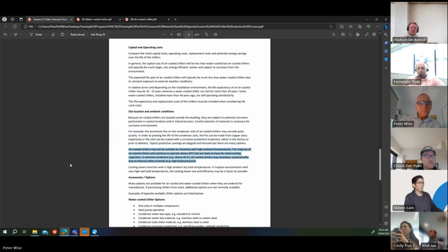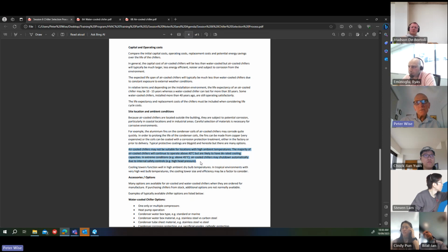Also, air-cooled chillers may not be suitable for locations with high ambient temperatures. The majority of air-cooled chillers will continue to operate above 40 degrees C, but are likely to have derated cooling capacities. So if you've got a situation where, say, it's in an environment that has a typical temperature in summer over 40, up to 45, look closely at the ratings on the chillers above 40 degrees. Up to 40, they're probably okay, and they'll give you the full capacity, but above that, they may not.